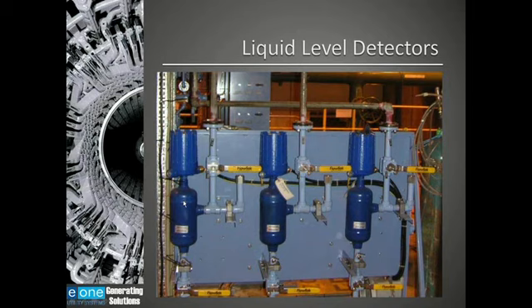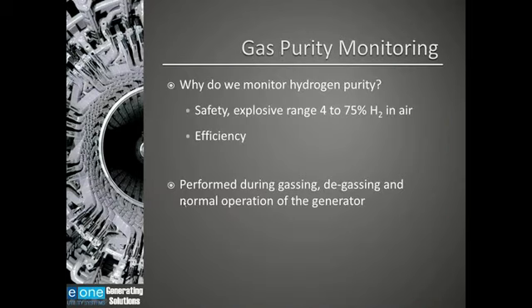Now I'm going to spend some time talking about gas purity, not just hydrogen purity, but gas purity in general. Why do we want to monitor the hydrogen purity? Two reasons. One is safety. When hydrogen is mixed with air, it becomes very explosive. It has a very large explosive range, 4 to 75% when mixed with air. We also want to monitor it because of the efficiency, as I indicated in that graph earlier. The purer the hydrogen, the less windage loss there is in the generator, the more efficient the generator is, the more megawatts that you can produce.